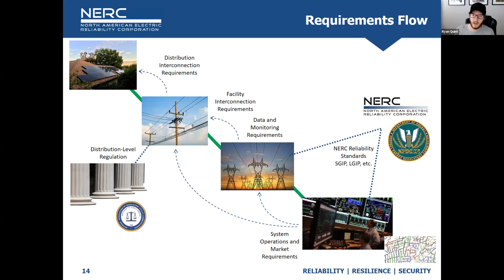But what's really important there is the distribution interconnection requirements, which would be applicable down to the individual DER owners. So then we turn that data flow backwards, and rather than requirements flow, we talk about data flow. When a resource interconnects to the distribution system, you gather information: the in-service date, the end of service date, the DER type, the DER kilowatt capacity, and the vintage of 1547 that was installed, which you could probably estimate from the in-service date.